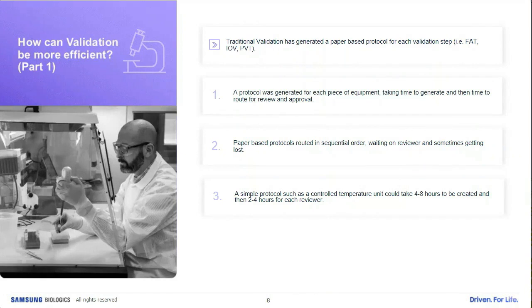And then we have simple protocols such as a controlled temperature unit, say a -70 freezer. A typical validation employee takes 4 to 8 hours to write a protocol just for a freezer, and then 2 to 4 hours for each one to review that protocol. It depends on how many signatures you need for review and approval of a -70 freezer. That could be 4 signatures times 2 hours, 8 hours.